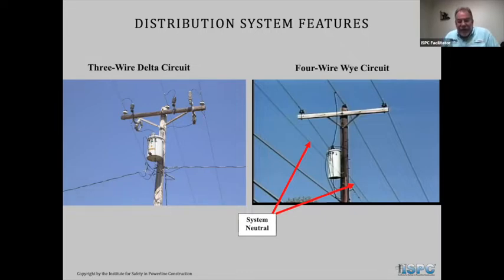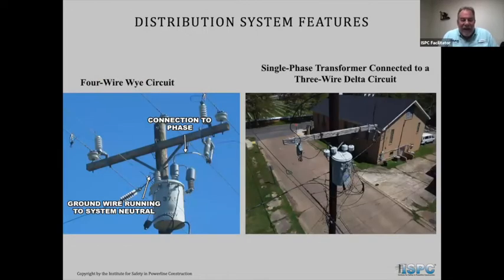However, if we have a situation where one of those energized conductors falls onto the system neutral or falls down onto a ground, the system protection devices that I'll talk about in a few minutes will trip as fast as possible because it is grounded. However, there will be an energized situation briefly on that line. So if I'm a telecommunication guy, I'm standing on a pole, I'm hooking up a service, and I'm touching that ground wire, would I get electrocuted? All I can say to that is the risk is very high.